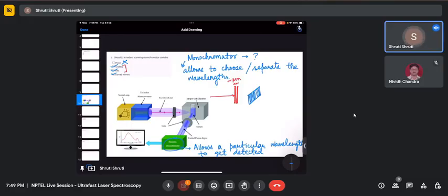But if we keep the averaging long, maybe 10 scans, 50 scans, then it will take more time to generate the spectra. So depending upon your sample, we need to adjust this parameter. Next thing is slit width. As I just told, slit width should be small.